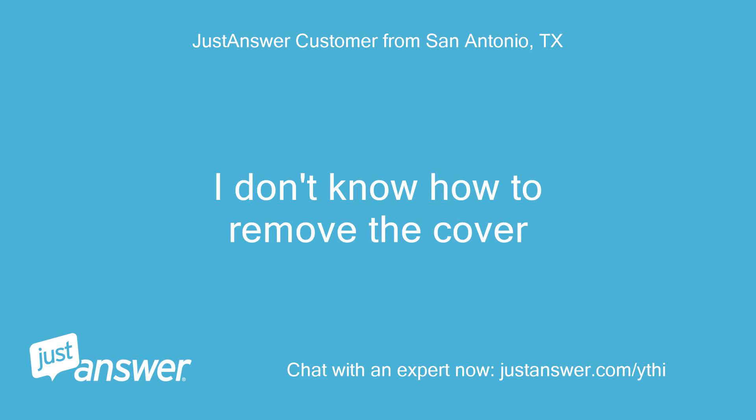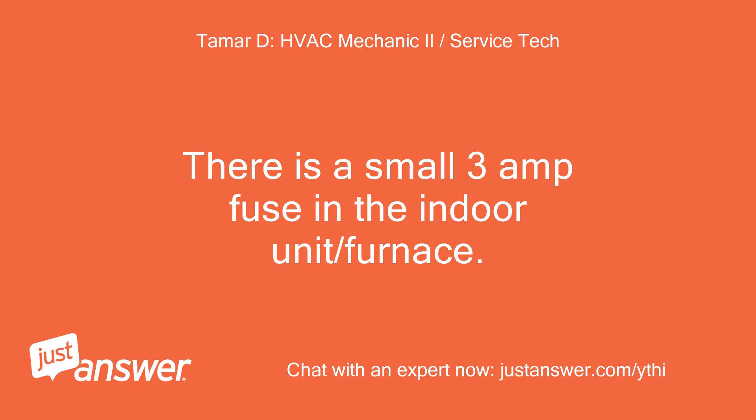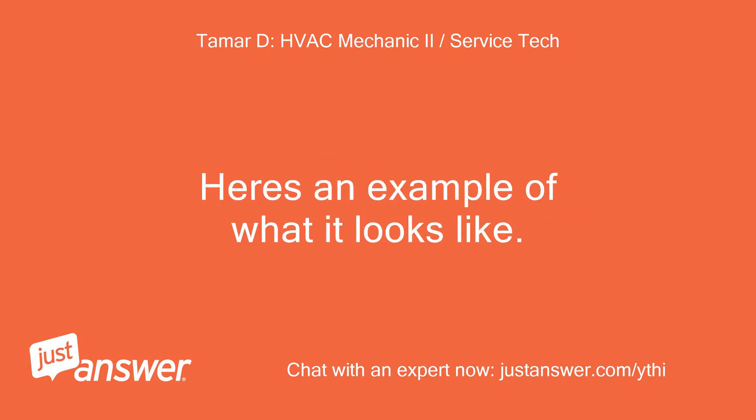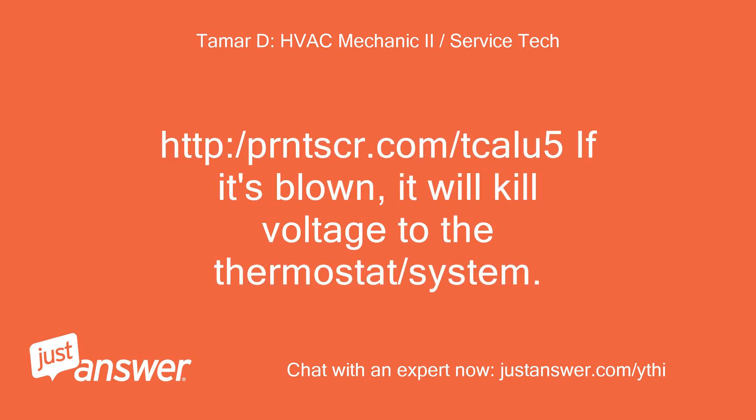I don't know how to remove the cover. There is a small 3-amp fuse in the indoor unit or furnace. It's usually stuck on the control board itself, and it's purple. Here's an example of what it looks like: http://prntscr.com/tcalu5. If it's blown, it will kill voltage to the thermostat and system.